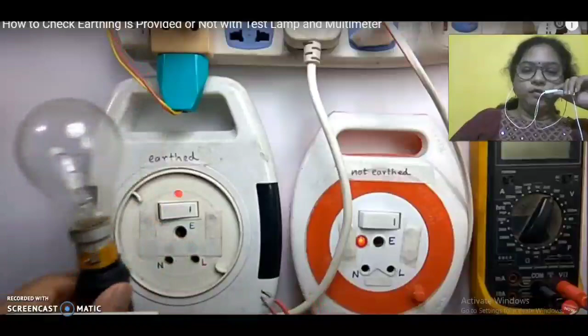You can use a multimeter, and insert it across phase and neutral, phase and earth, and neutral and earth. Suppose your phase and neutral voltage is 235, which is the actual single phase supply, and phase and earth voltage is 233, so you might think that your earthing is there, but whether earthing is proper or not, you can check with the help of the multimeter by checking its leakage voltage. The leakage voltage is the voltage difference across phase and neutral and phase and earth, that is here 235 minus 233, it is 2 volt, plus neutral to earth, it is 1.3, so it is coming as 3.3 volt. This is less than 5 volt, so your earthing is proper and of good quality.